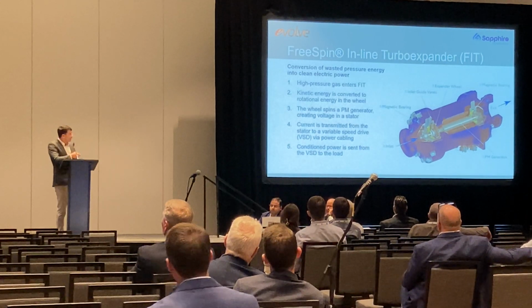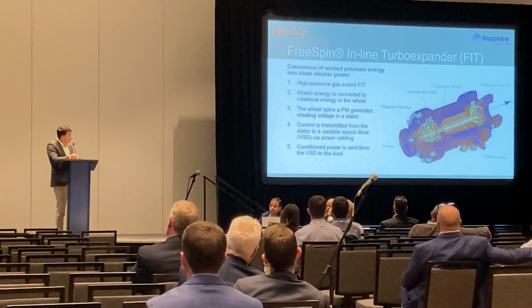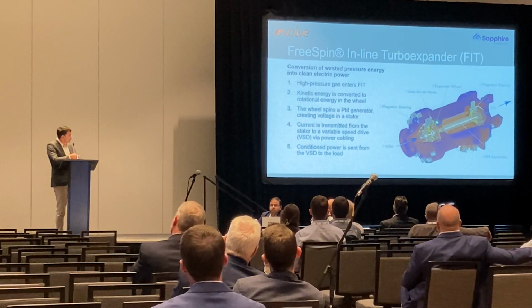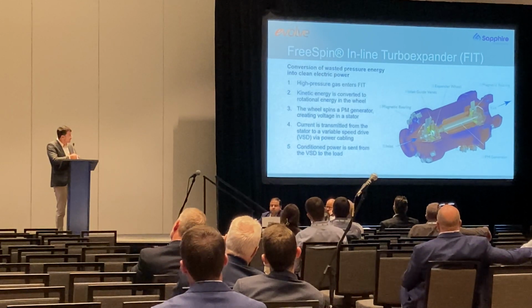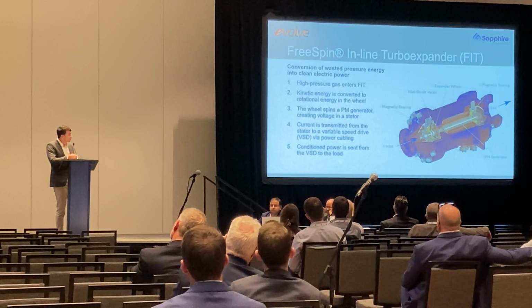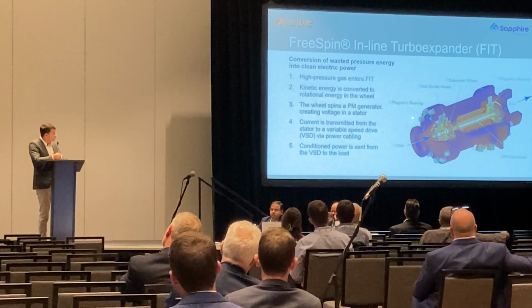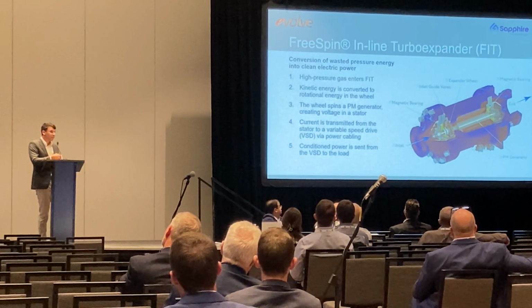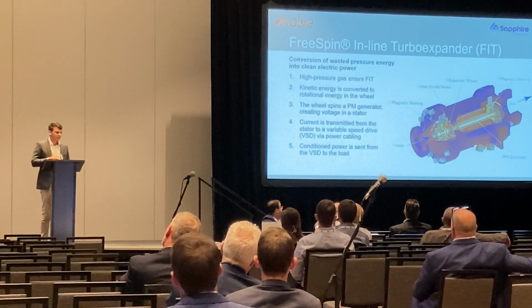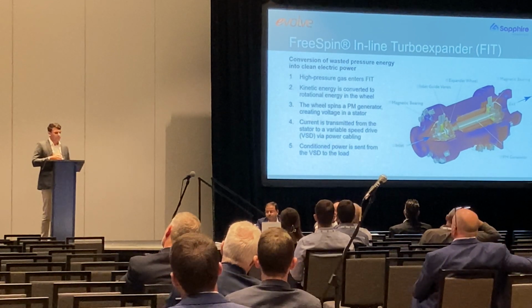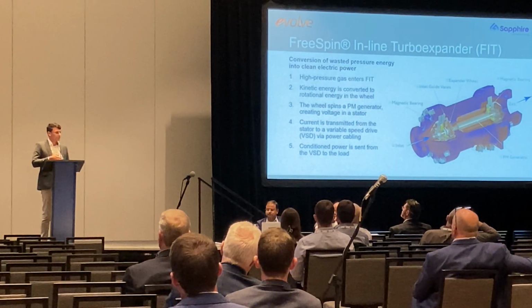High pressure gas enters the expander on the inlet side, directed via a nozzle into the expander wheel. The wheel is directly coupled to a permanent magnet generator, so as gas spins the wheel, the generator spins with it, and a voltage is developed in the stator. We pull the current out of the system and direct it to our power electronics unit, which we call our variable speed drive. The power is conditioned there to a usable frequency and voltage, and the end user uses it to power the load.